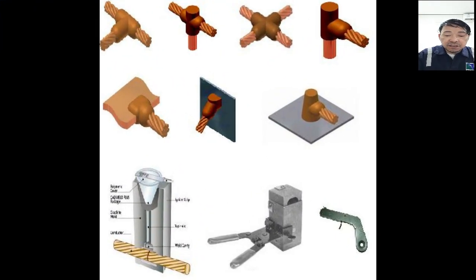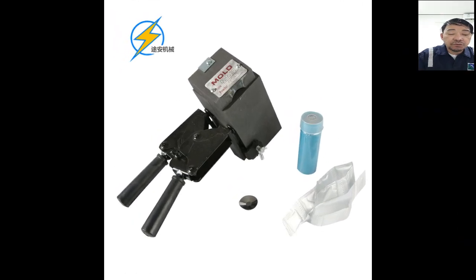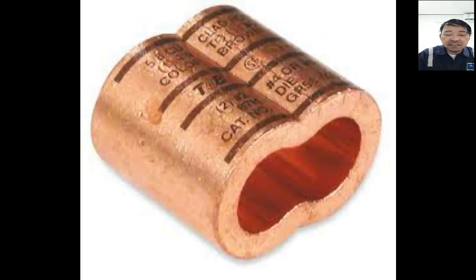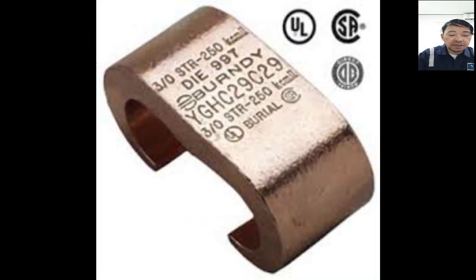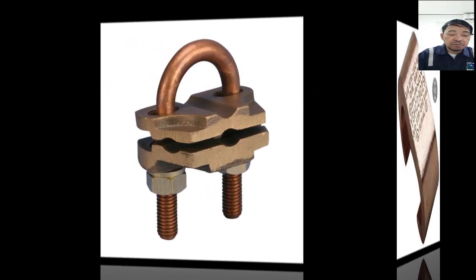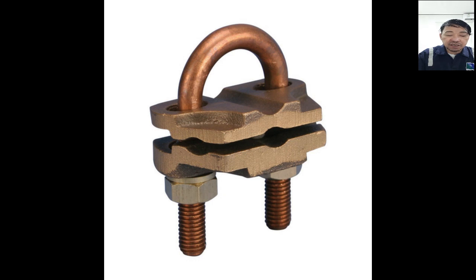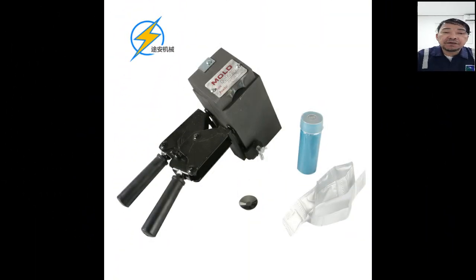Below ground connection to grounding grids and ground rods, or between conductors or grounding rods, shall be made using one of the following: by thermite welding or brazing; by an irreversible compression type connector listed as grounding and bonding equipment, and having a manufacturer reference compression die number and conductor size printed or stamped on the connector. And the third one is by mechanical connector, which is necessary to disconnect ground conductors for tests at the ground test station. We will be having separate videos for the CAD welding or thermite welding.